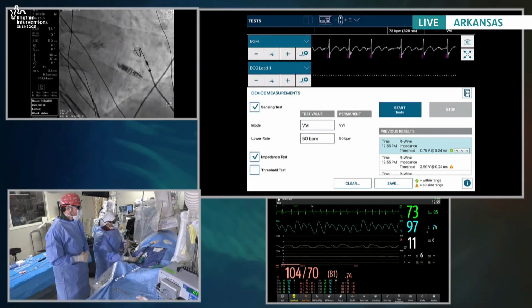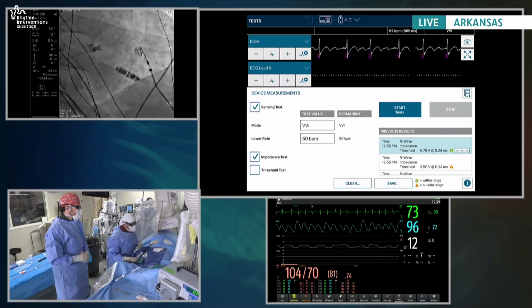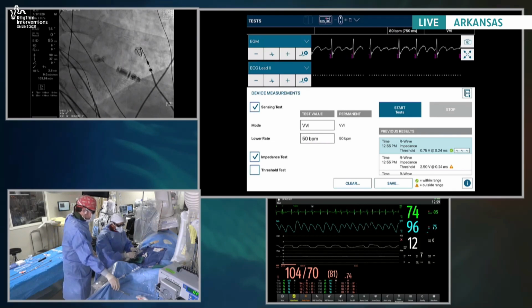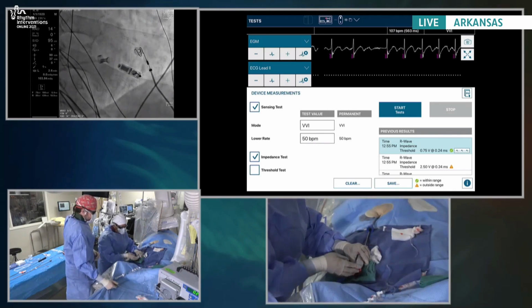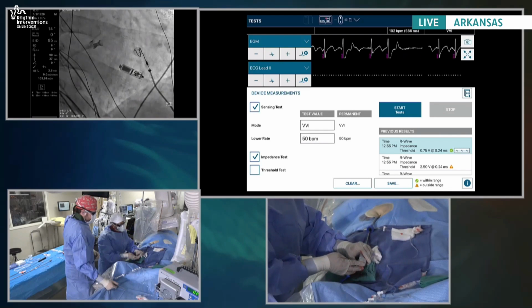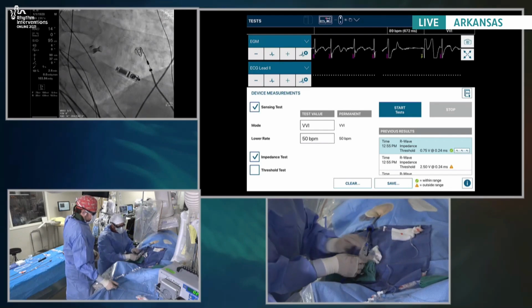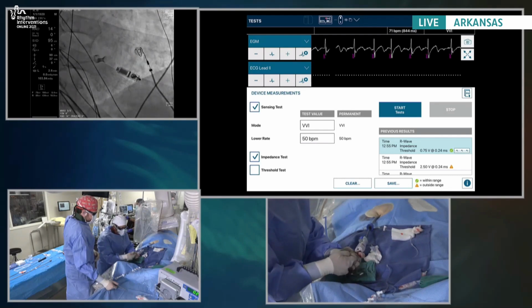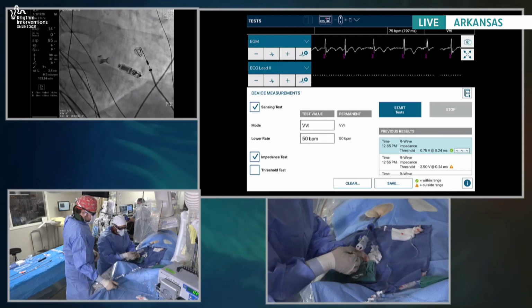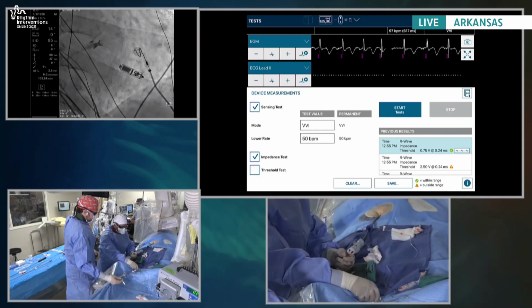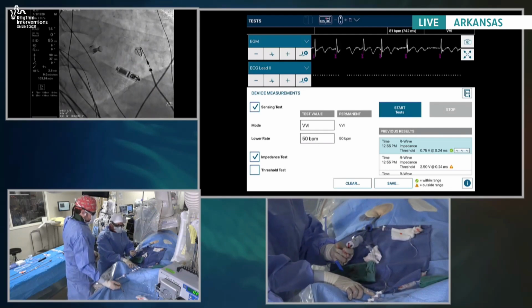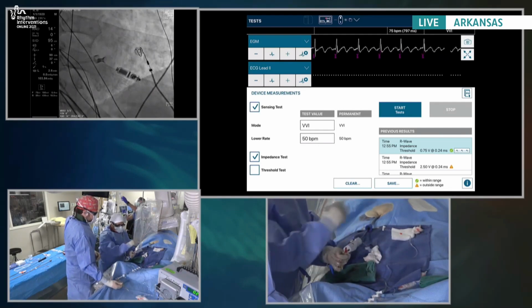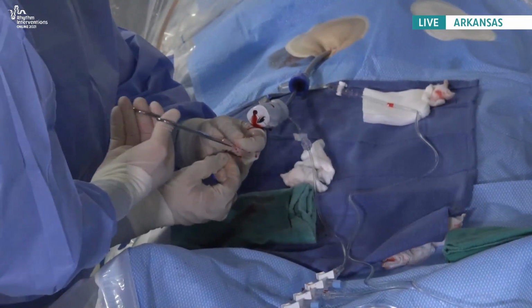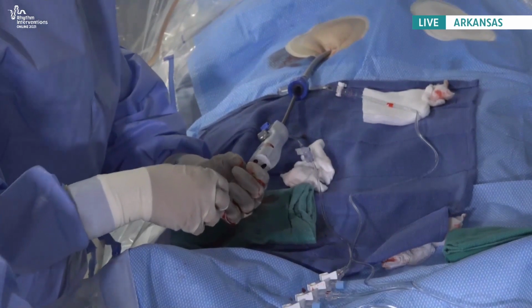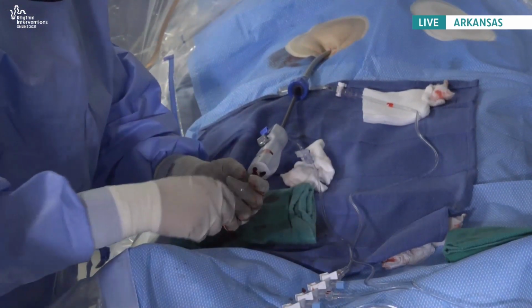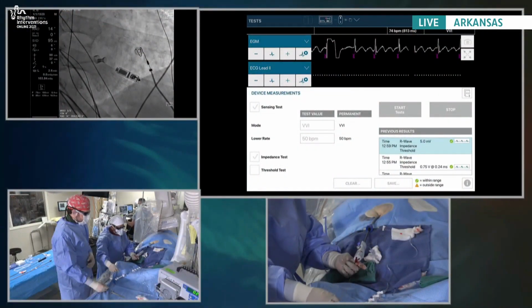So we have very good numbers. We have, say that again, 0.75 at 0.24 milliseconds. So that's a very good number. We are going to go ahead and flush the system. So this is the time we're going to release the device. I flush the system, make sure everything is good. And as the flush is happening, I kind of floss these tethers here to make sure that it's all good. We want to make sure we stop the flush before we cut this tether. You don't want the tether to get all bundled up with the flush going in. So we're going to cut off one end of it and slowly, kind of go with the heart's beat, slowly release the device. So we're going to pull this out.